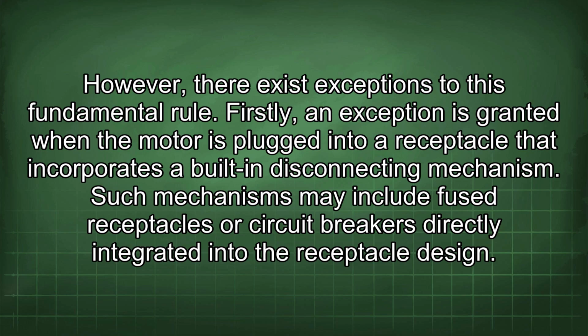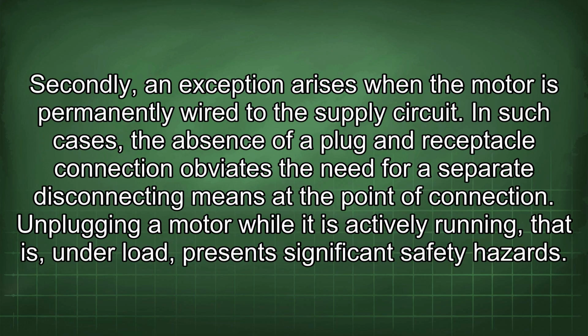Firstly, an exception is granted when the motor is plugged into a receptacle that incorporates a built-in disconnecting mechanism. Such mechanisms may include fused receptacles or circuit breakers directly integrated into the receptacle design. Secondly, an exception arises when the motor is permanently wired to the supply circuit. In such cases, the absence of a plug and receptacle connection obviates the need for a separate disconnecting means at the point of connection.